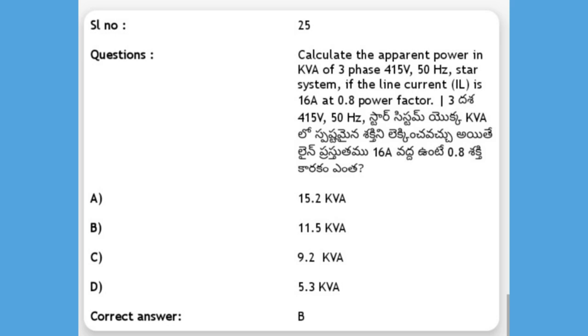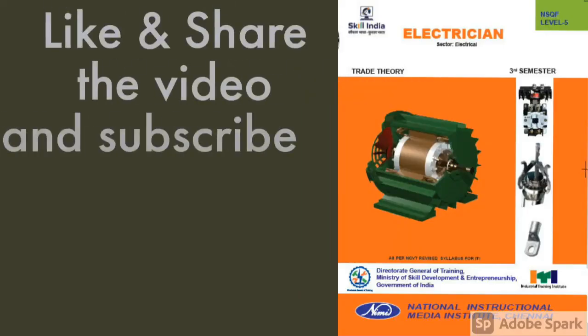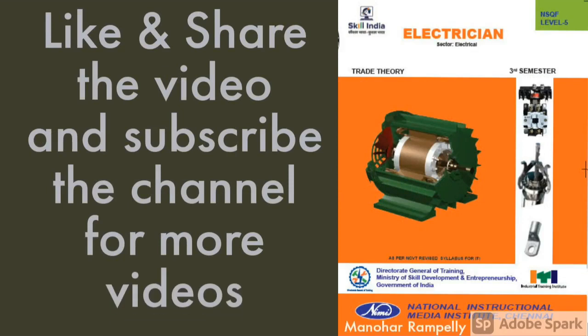The apparent power formula is: √3 × V_line × I_line. So, √3 × 415 × 16 = 11,500 VA = 11.5 KVA.